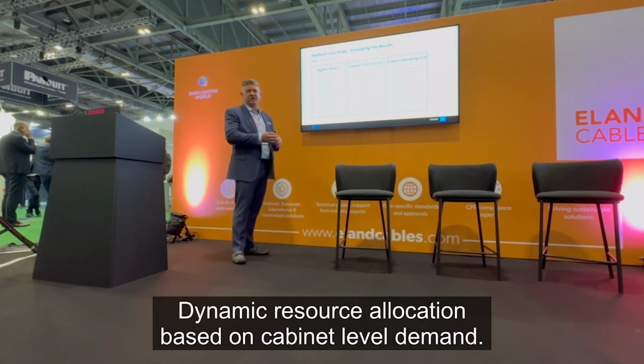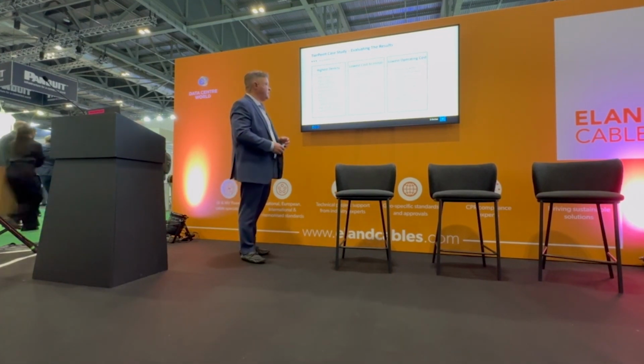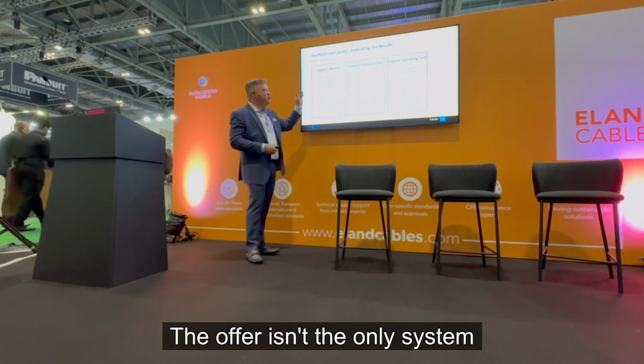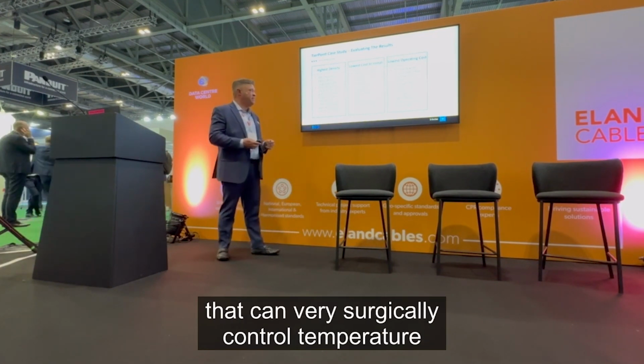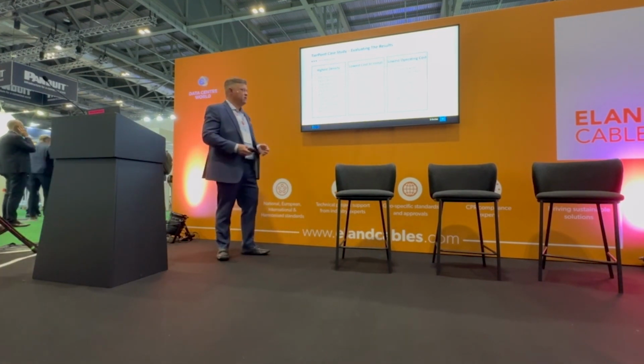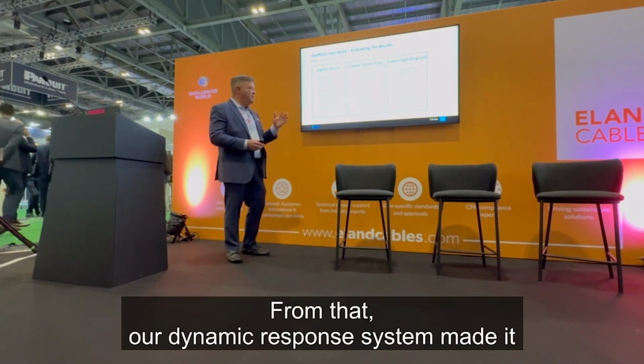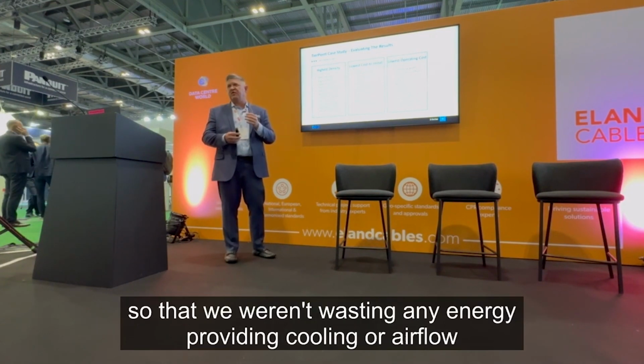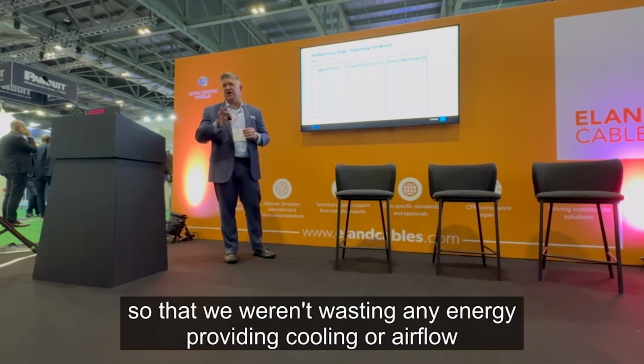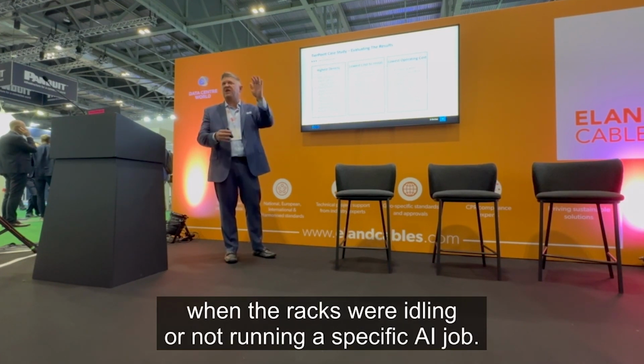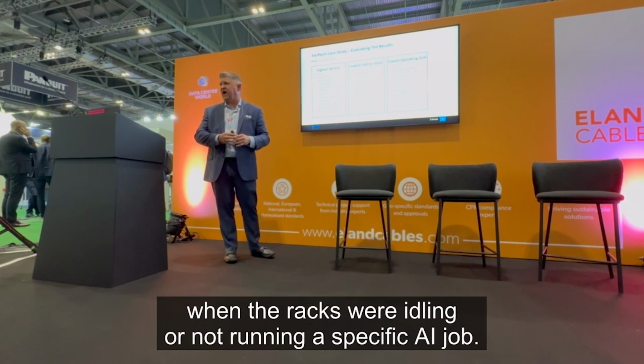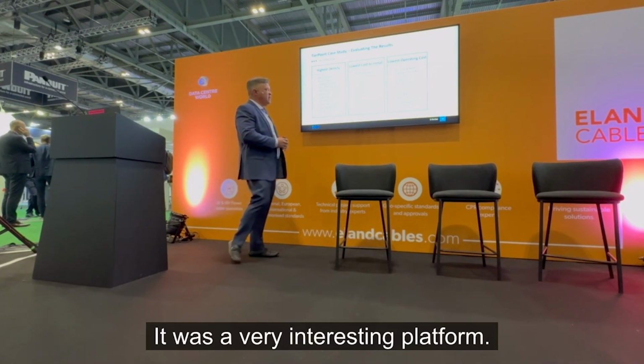So regardless of whether the customer workload goes up or down in real time, the system will adjust the water and fan speed so that you're not wasting or stranding any resources in the data center. Dynamic resource allocation based on cabinet level demand. We offer the only system that can very surgically control temperature both at the front and back. And our dynamic response system made it so that we weren't wasting any energy providing cooling or airflow when the racks were idling or not running a specific AI job. So it's a very interesting platform.